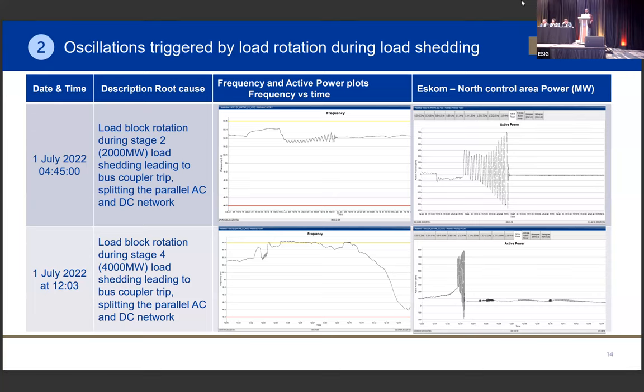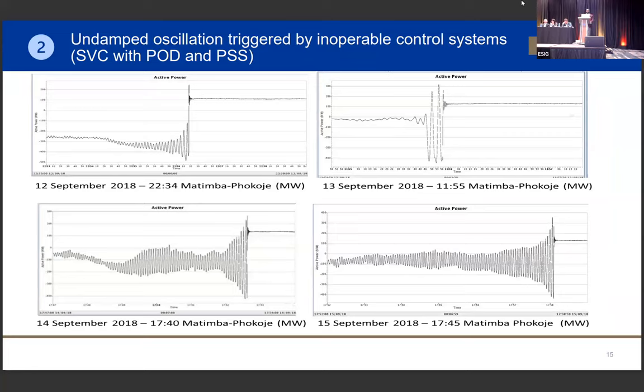Second graph, a similar thing. High frequency, the bus coupler tripped, and the oscillation started. Then we reached 50.5, which is high frequency on our side. Another type is whenever we have control systems that are inoperable, like SVC or POD, if not available in one of the countries, or some PSS that are not tuned correctly, any small disturbance can lead to power oscillations. This is the week of September 12 to around 12, 13, 14, 15. Every day we had such incidents. That week we didn't have both critical power oscillation dampers in the network.